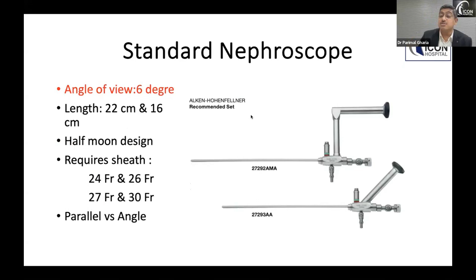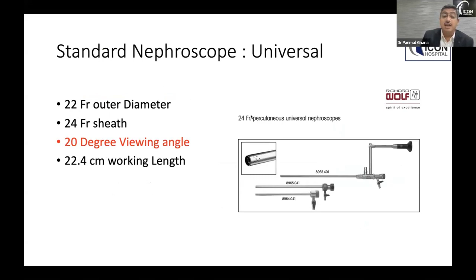So this is a standard nephroscope which has a half moon design, mostly made by Storz, and it requires a 24 or 26 sheath. Then another is a universal nephroscope by Wolf. It has a 22 French outer diameter, requires a minimum 24 French size sheath, and it has a 20 degree angle of view.